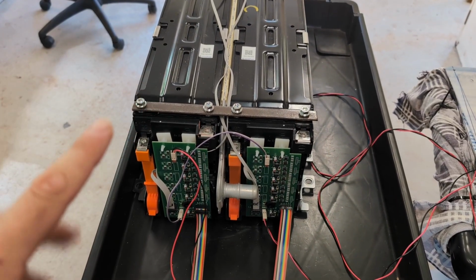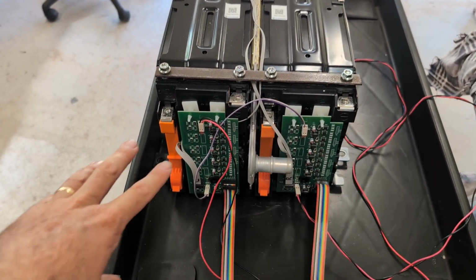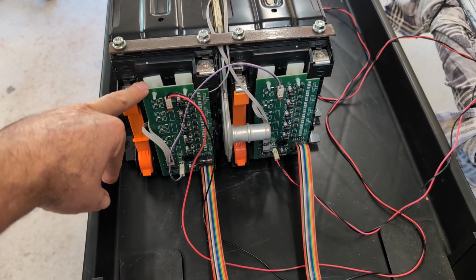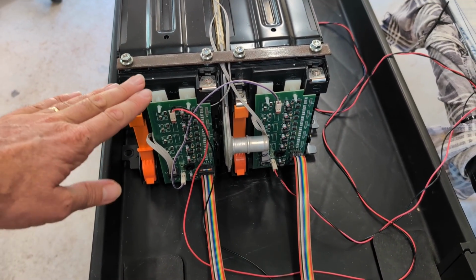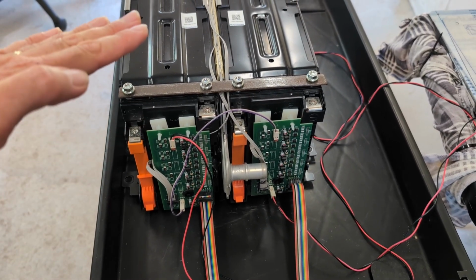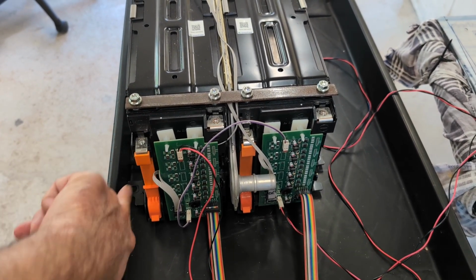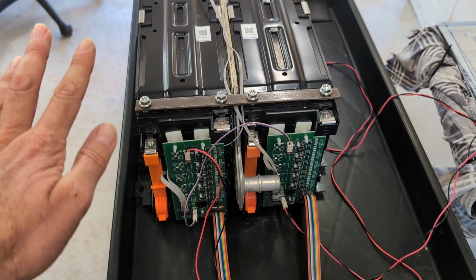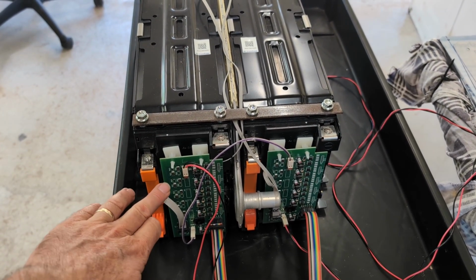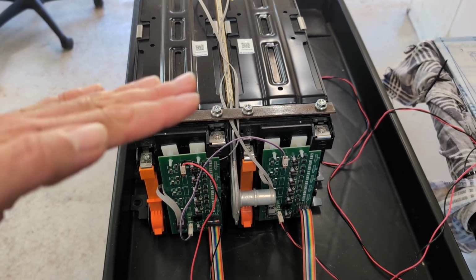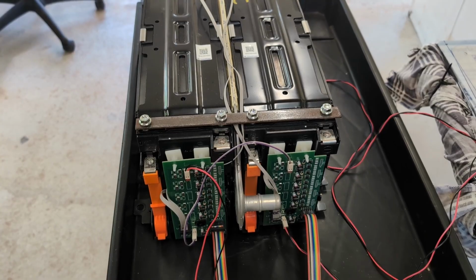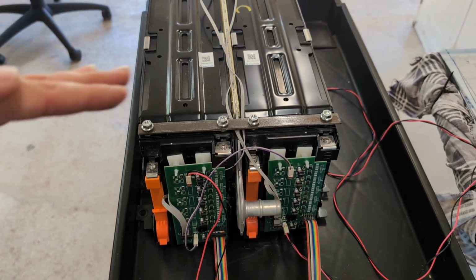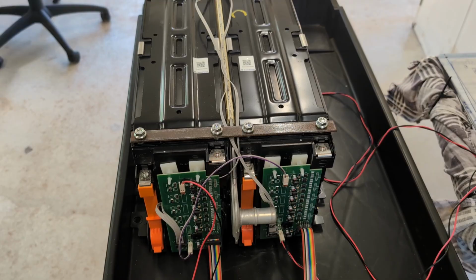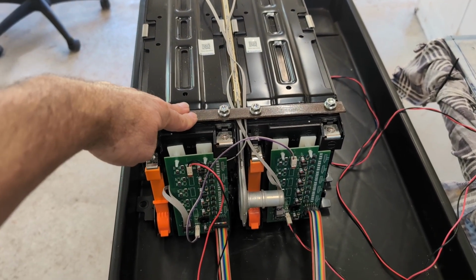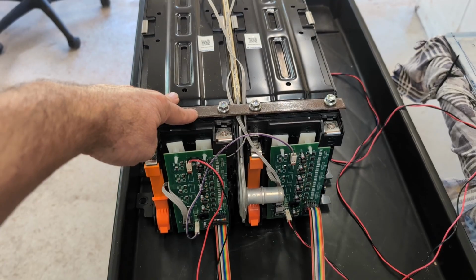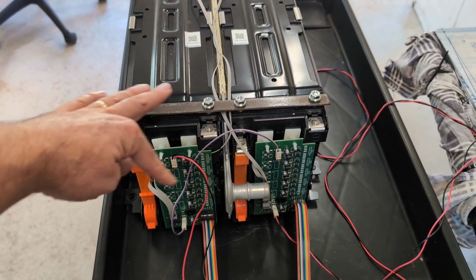Next thing to test is the balancing resistors. This battery management system will check the voltages of all the cells, and if there's any high cell voltages, it will connect these resistors across the cell, and that will use up some of the power, just make heat in these resistors, and it'll slowly bring the voltage of that cell down, and do that only for the high ones until they all come to the same. So that's the balancing function. We're going to test that. Because these cells are all the same voltage, it won't run any of these as we've just had it with these 12 here at the moment.